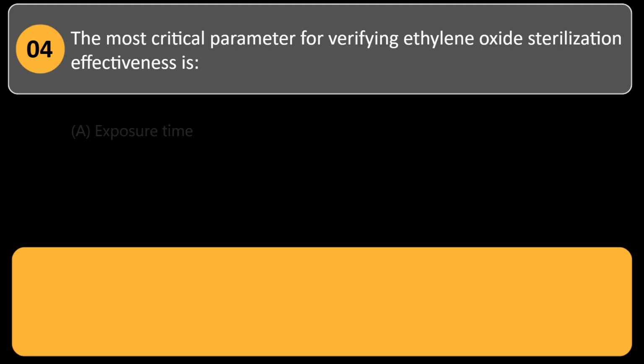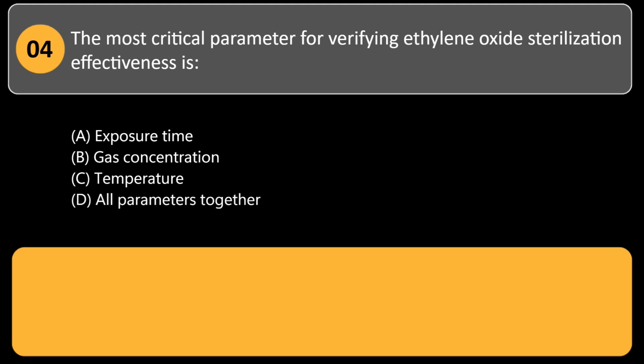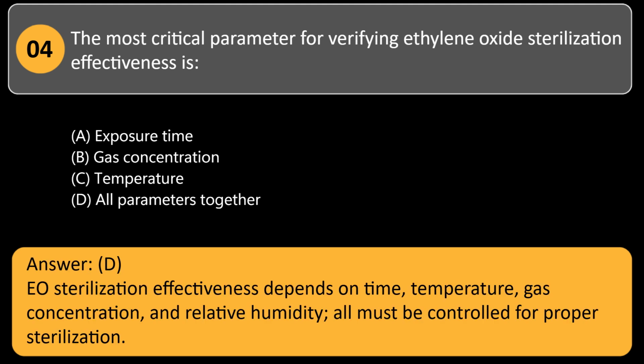The most critical parameter for verifying ethylene oxide sterilization effectiveness is A. Exposure time. B. Gas concentration. C. Temperature. D. All parameters together. Answer: D. EO sterilization effectiveness depends on time, temperature, gas concentration, and relative humidity. All must be controlled for proper sterilization.